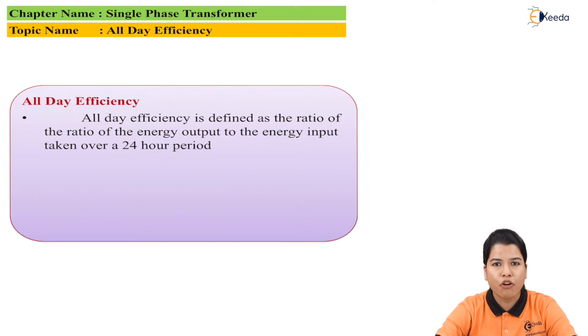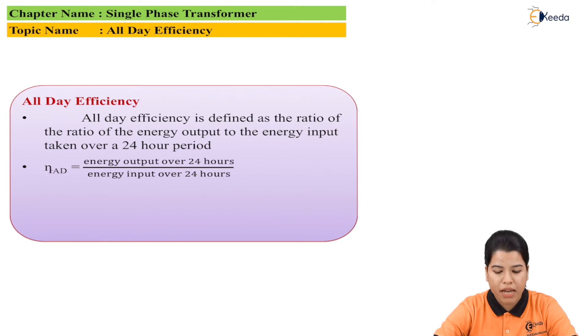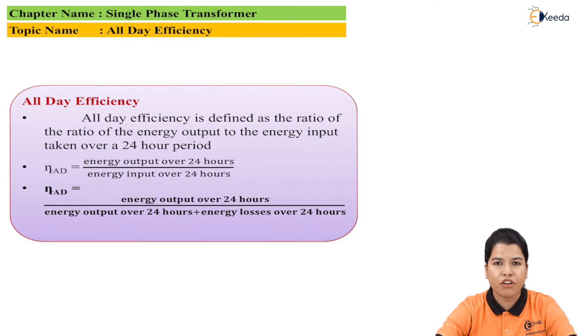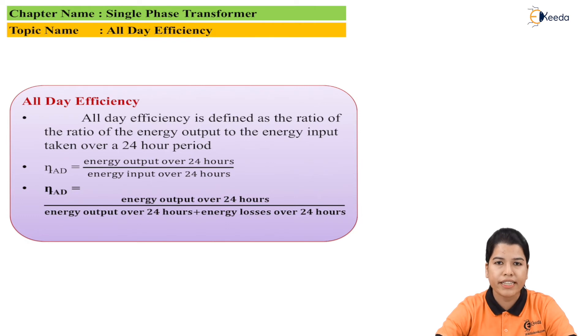We know that input is nothing but output plus losses. Hence this equation can be modified as: all day efficiency of the transformer is given by energy output over 24 hours divided by energy input over 24 hours. This can further be expressed as energy output of the transformer in 24 hours divided by energy output of the transformer in 24 hours plus the total losses of the transformer in 24 hours. In this way we can calculate the energy efficiency or all day efficiency of the transformer, which gives a better performance result for the distribution transformer.